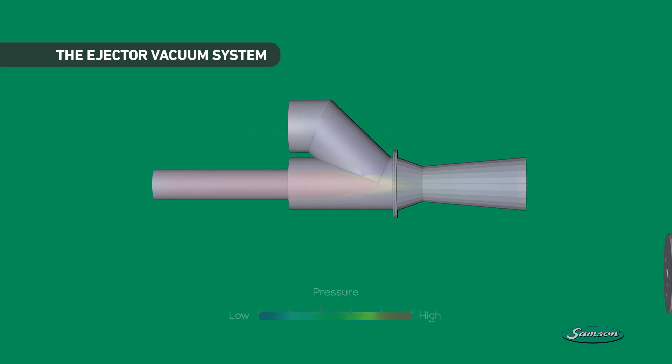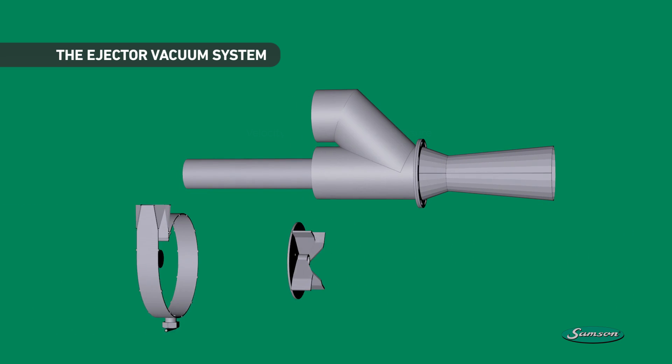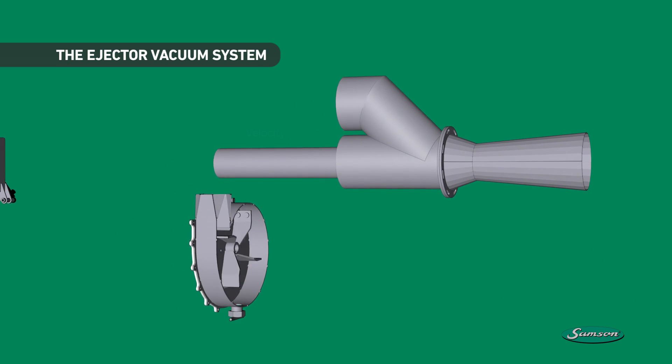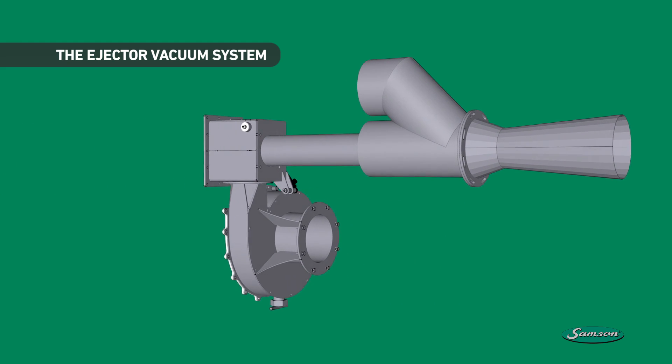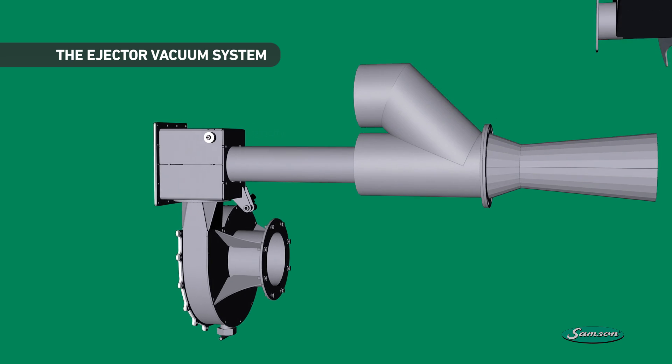The Samson Ejector Vacuum System uses a robust centrifuge pump with a heavy-duty semi-open impeller to drive the flow of fluid to the ejector. A centrifuge pump like this needs priming and must be fully submerged to function.